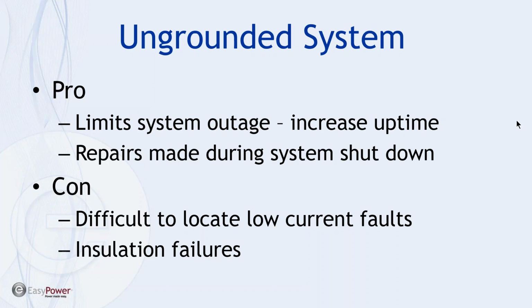Trouble is, when you had multiple faults like this, it's difficult to locate the low current faults. And if you have a system that tolerates a number of low-level ground current flows, you have the potential, over the long term, for deterioration of your insulation, which has other issues and can result in things like arcing faults, in addition to hard faults down the road.